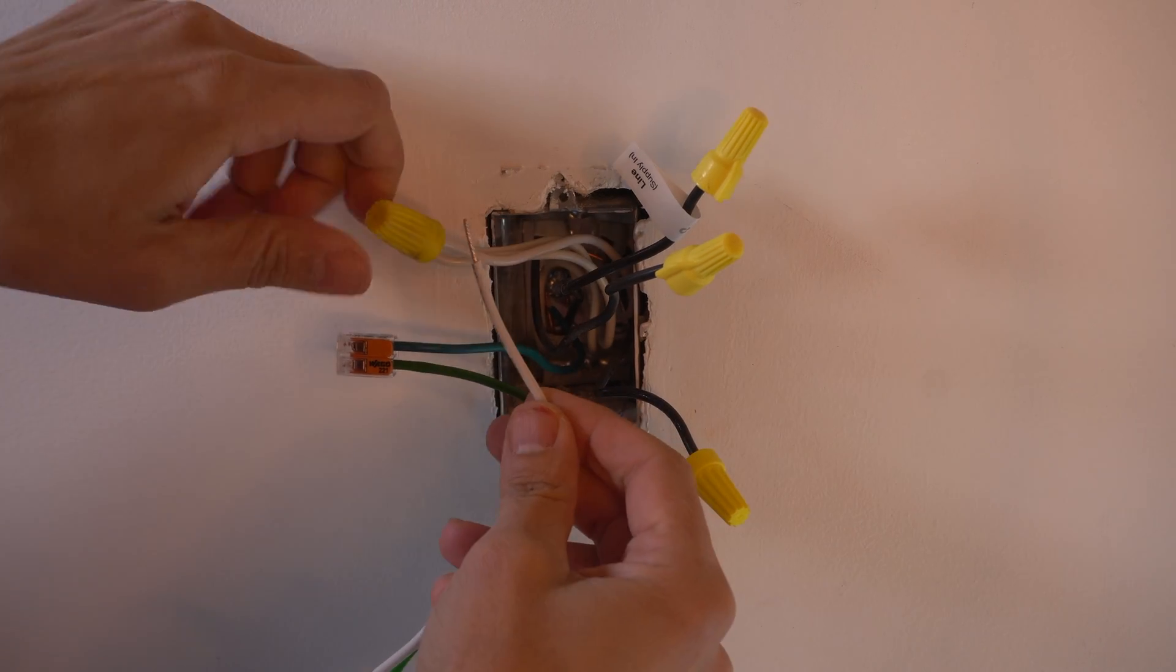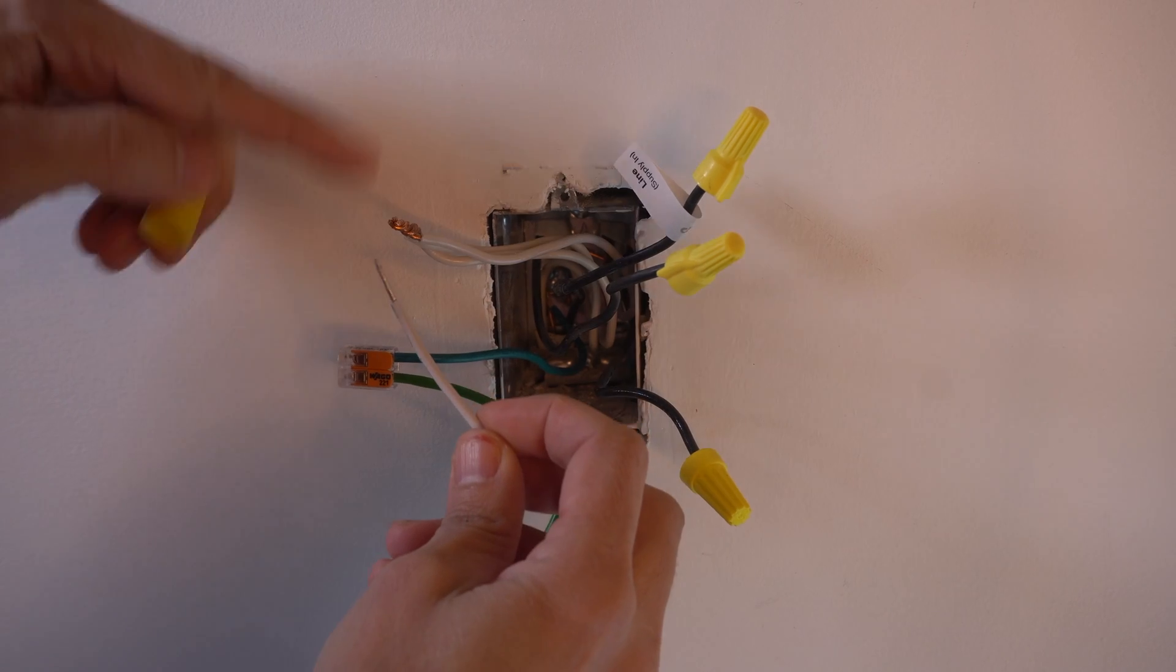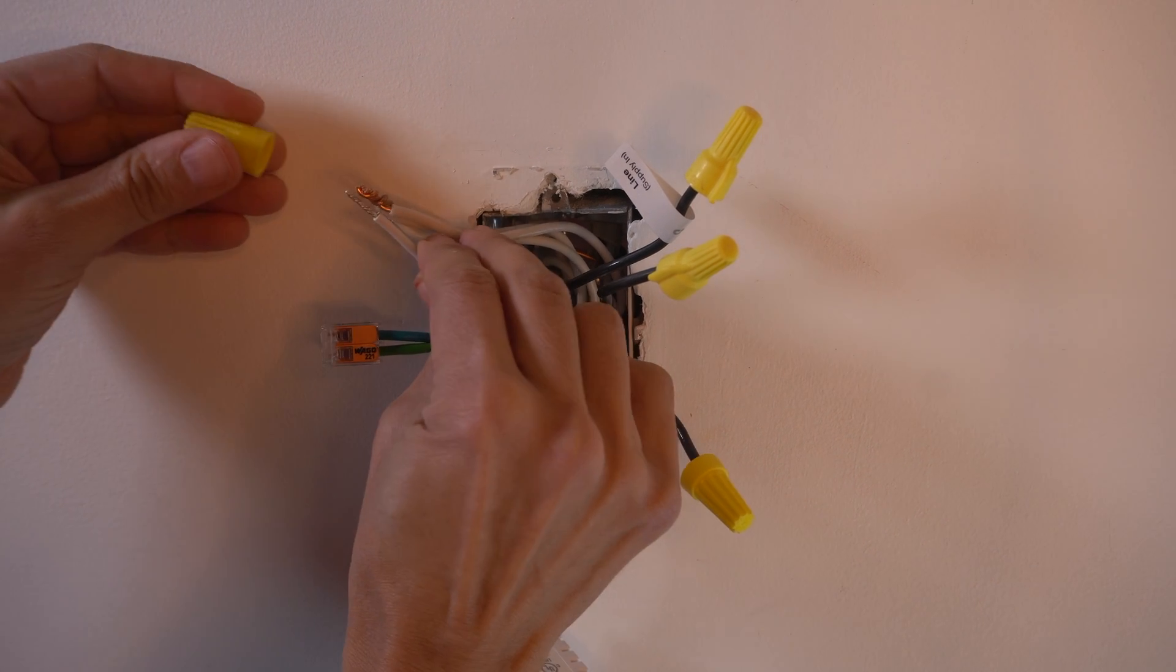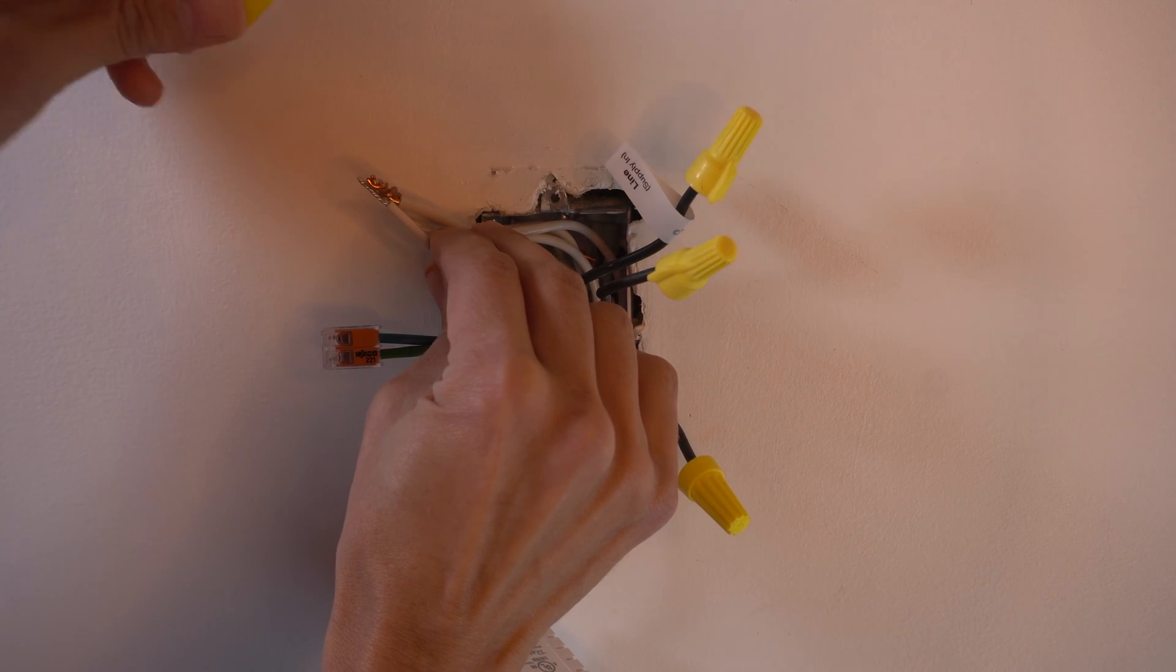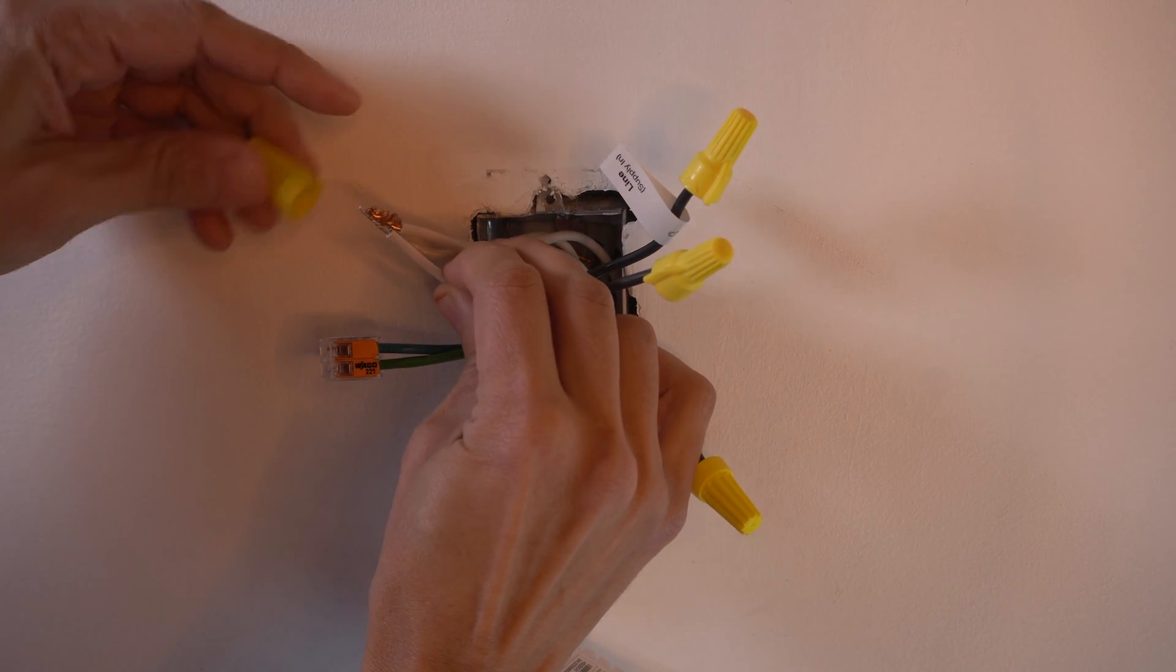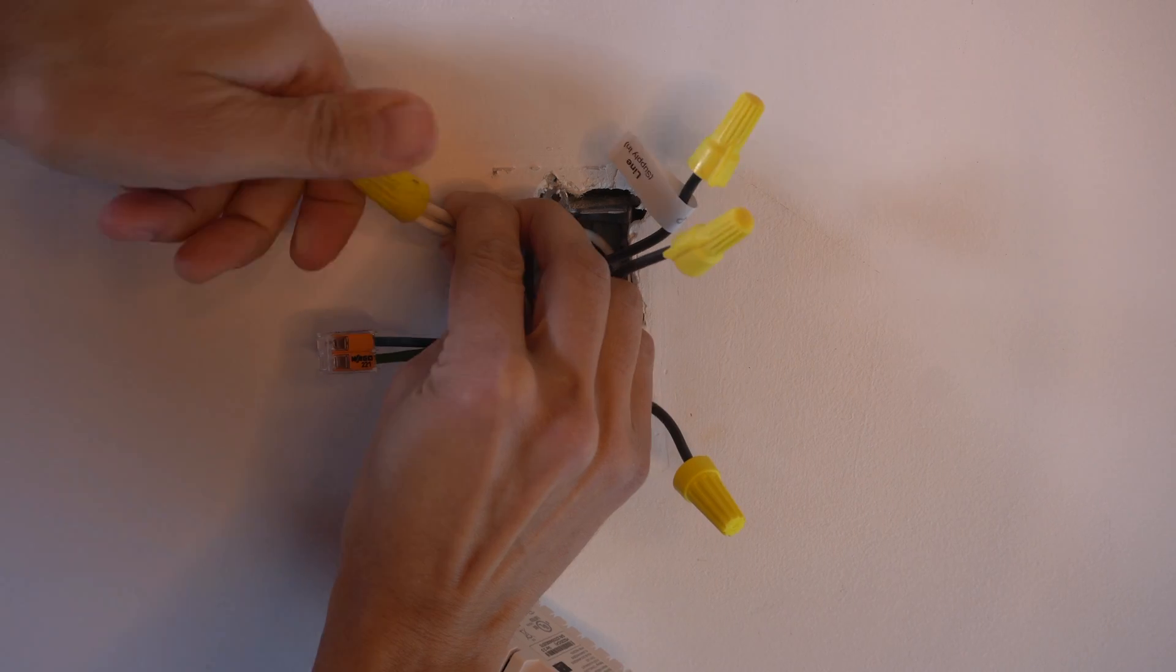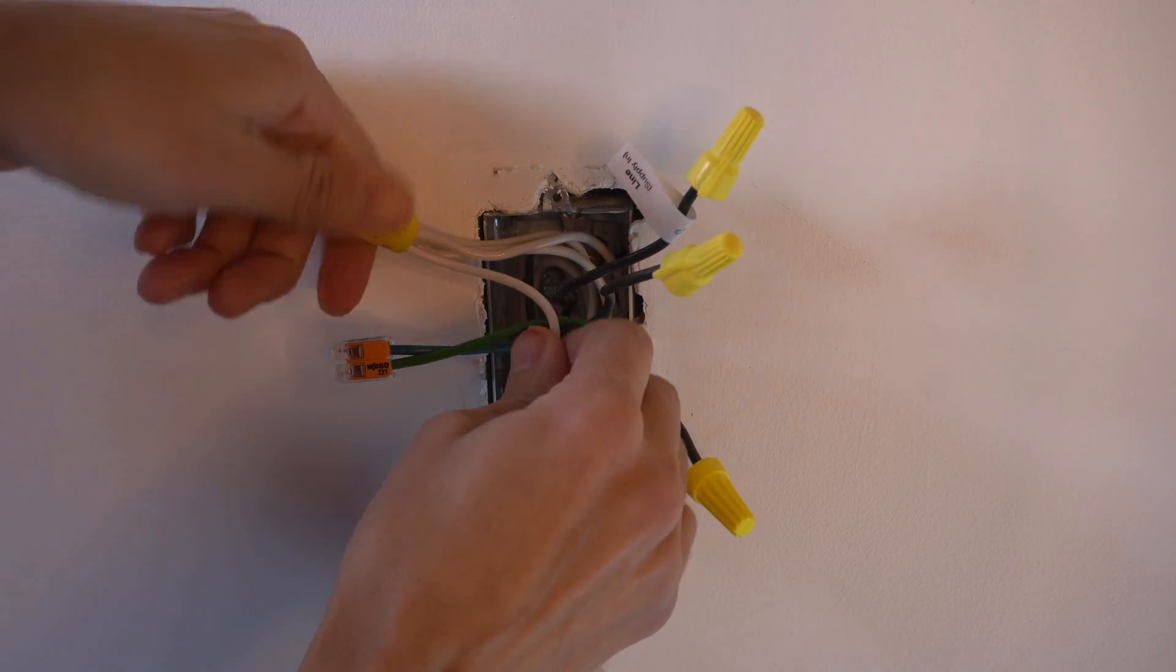We'll do the wire nut here on our neutrals. See that? That's actually been twisted. Typically good electricians - you see how that's nicely twisted? That's how we do it here. You can lead with this by about a quarter of an inch or you can twist that as well with your linesman. We do want it to lead. Put that tightly on. The best electricians, when they use wire nuts, will do the pre-twisting.